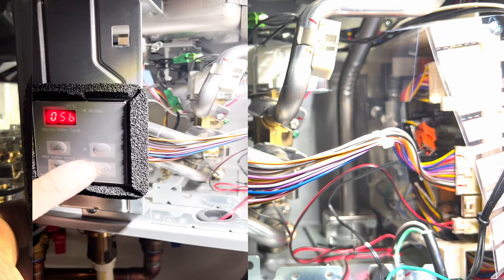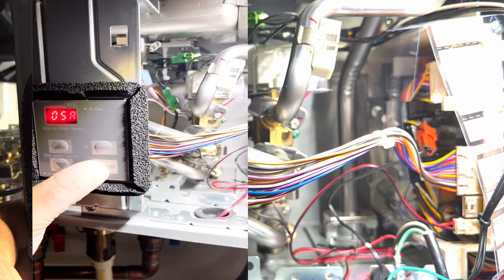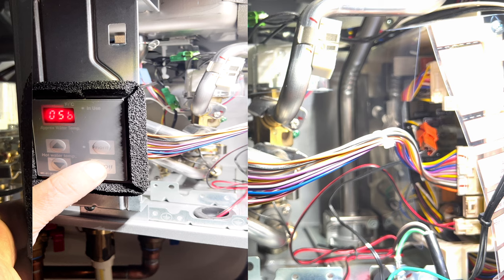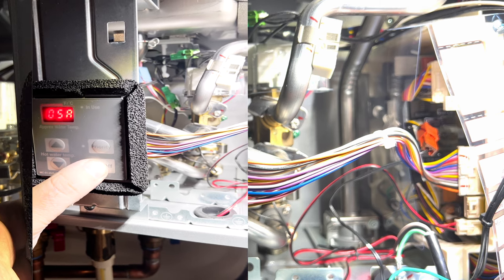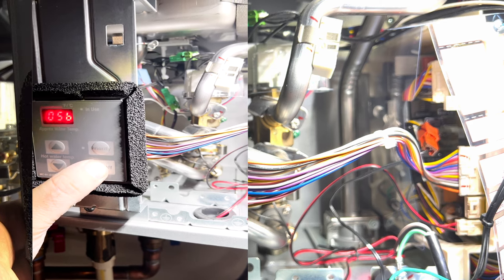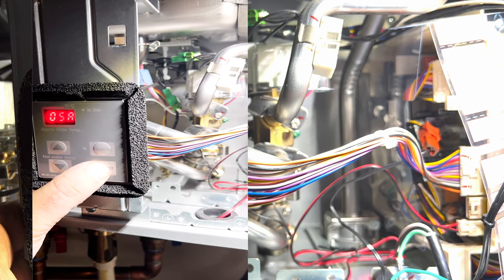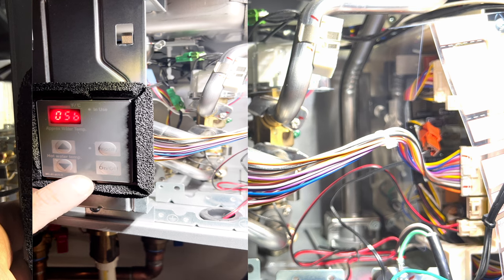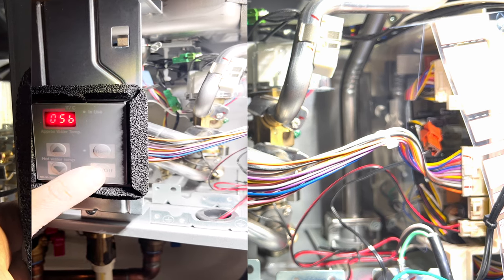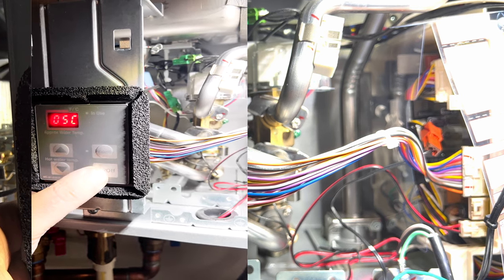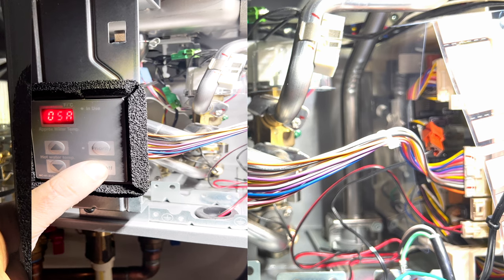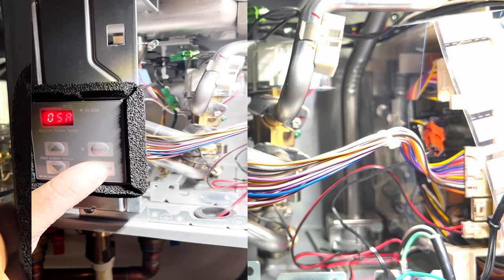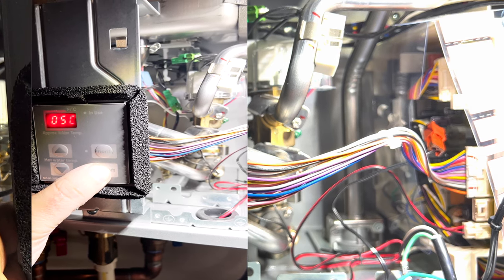Setting 05 becomes available after the circulation pump is turned on. Default selection here is A which stands for economy. Selection B is for comfort. In economy mode, the instant hot water feature runs less often, prioritizing energy savings. While in comfort mode, the pump runs more often, prioritizing hot water at your taps.